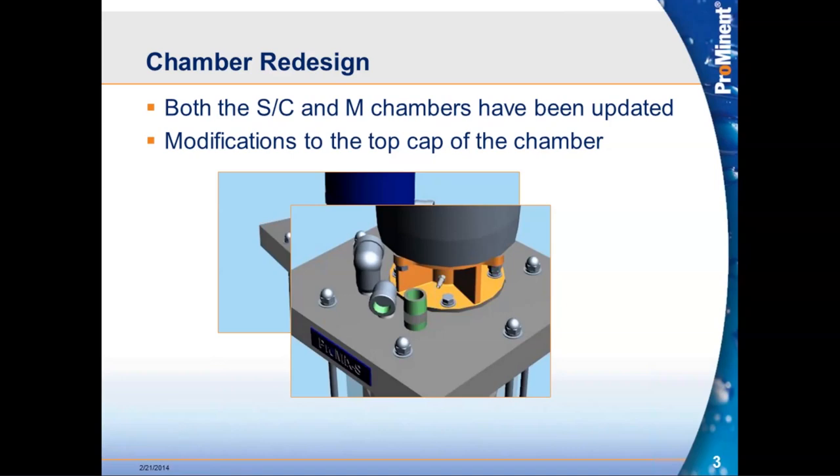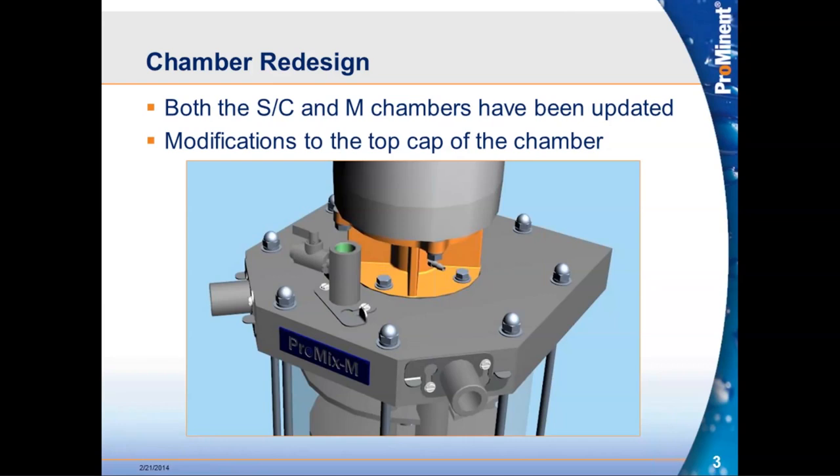The solution was to modify how that top was built. We moved the water inlet and the polymer make-down outlet to the sides of the chamber, freeing up space on top. Now the only thing on the top is the actual polymer injection point. The inlets, outlets, and polymer injection point all utilize a twist-lock configuration for those connections, giving operators a much easier way of getting fittings in and out during maintenance.